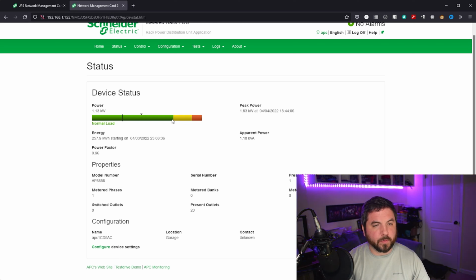And you're within the normal range if you're within 3 kilowatts, 0 to 3 kilowatts. So not even close to hitting the danger near overload. And you can actually track the kilowatt hours that the PDU registers, and then you'll see how much kilovolt amps you get and the power factor. And then here's a little bit more about the model, the serial number, phases, metered phases. And I think these would be different if you had maybe a switched PDU. You can name your device if you want to. You can set the location.